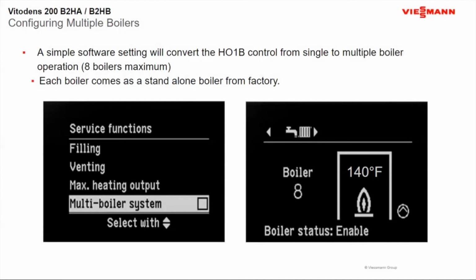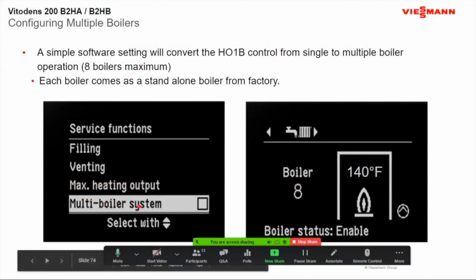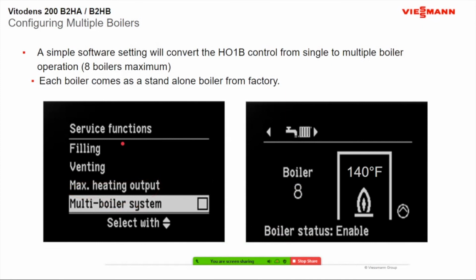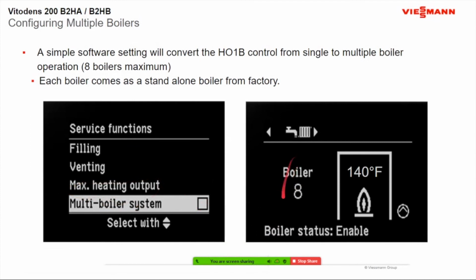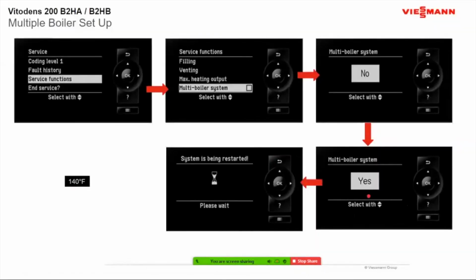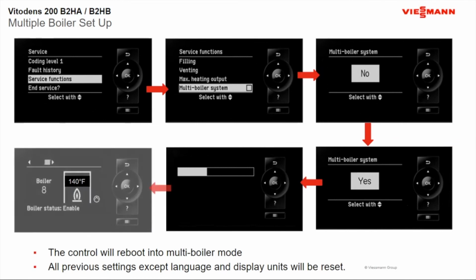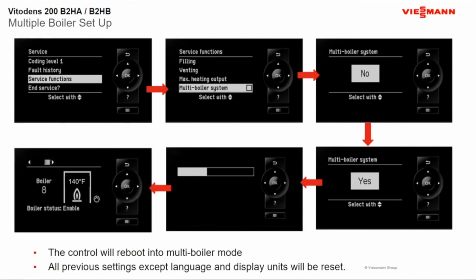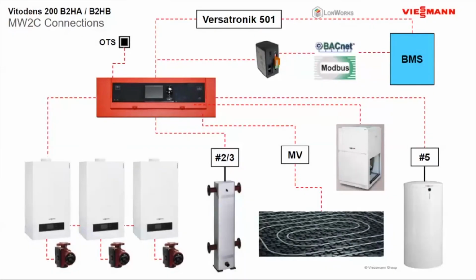But that means you would remember in that service functions, we saw that multiple boiler setup. If you're going to do multiple boilers, first you have to set up the boilers to put it in multiple boiler system. So you would go into that service function, click OK, put the check mark in that box. You'll see the boiler reboot, and now come up with a totally different screen for multiple boiler setups. So it does have a startup wizard as well. You'll see it reboot. Come up to this screen here, and then there's a little more programming as well for that. It's a different class, but it's pretty quick and painless as well for setup. As you see, these boilers are getting easier and easier to set up, and with self-auto recognize, it's a pretty easy setup.